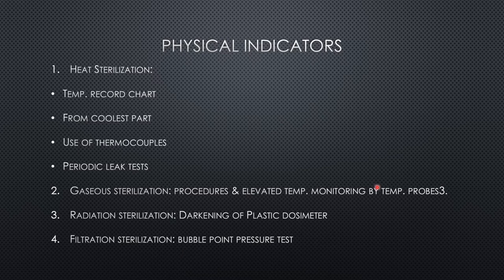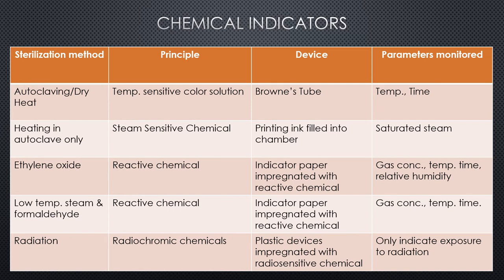Now we will move towards chemical monitoring of the sterilization process. Chemical monitoring is based upon the ability of heat, steam, sterilant gases, and ionizing radiations to alter the physical characteristics of a variety of chemical substances. This change should take place only when the sterilization cycle has been successfully completed, and this change is considered as a sterility check. The ideal indicator response is not always achieved. Chemical indicators generally undergo melting or color change, with the relationship of this change to the sterilization process being influenced by the design of the test device.